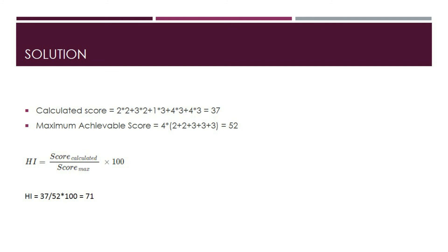We first calculate the calculated score, which is the sum of the ratings multiplied by the weight of that category. In this case, the number is 37. Then we calculate the maximum achievable score, which is 4 times the sum of all the weights, and that equals 52. The health index formula is score calculated over score max times 100, so 37 divided by 52 times 100 equals 71. As mentioned in the fundamentals previously, a value between 70 to 85 is considered good, and as such, there might be deterioration of some components and only normal maintenance is needed.